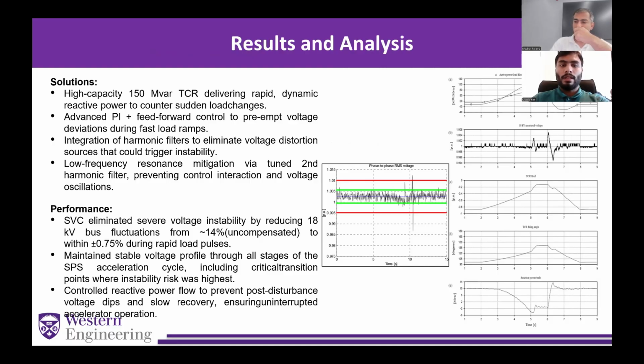So they installed a 150 MVAR SVC to preempt voltage deviations and to filter out harmonics. As we can see on the graphs, I'm particularly talking about the graph with the green line, we can see that the voltage is stabilized around 1 per unit. And on the right side, we can see the SVC output. We can see the firing angle of the SVC. We can see the injected or absorbed reactive power by the SVC. Due to this, the fluctuation significantly dropped from 14% to 0.75%, and it increased the system's voltage stabilization. Next slide, please.